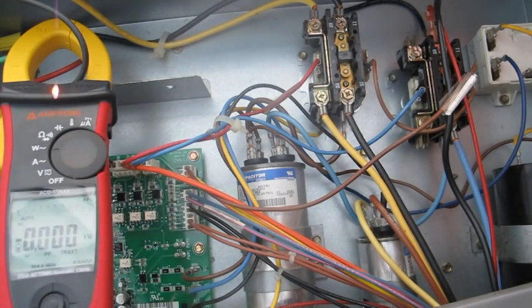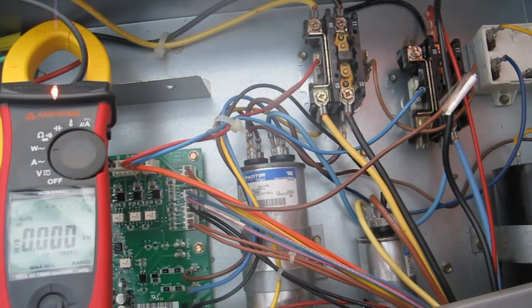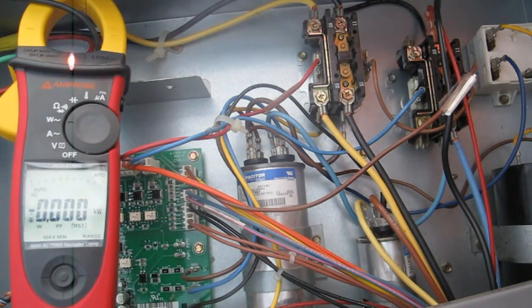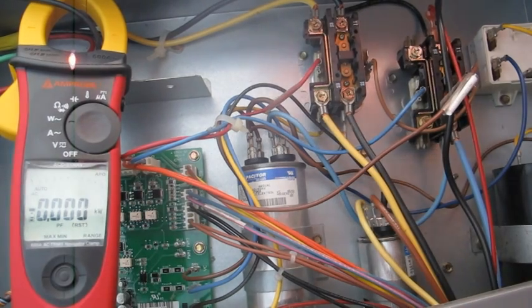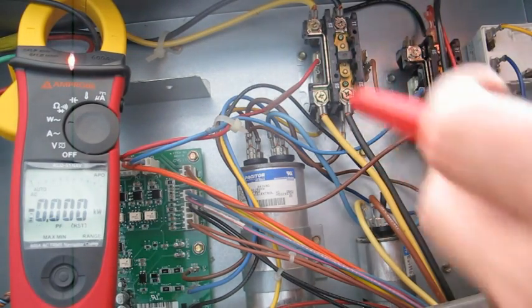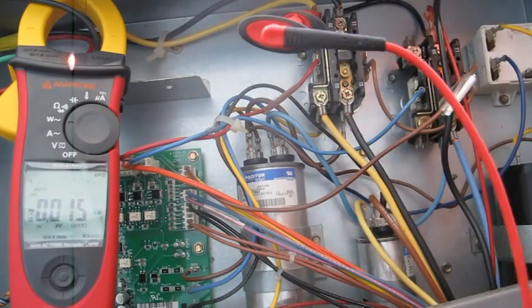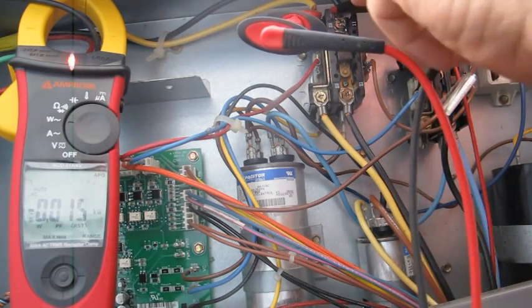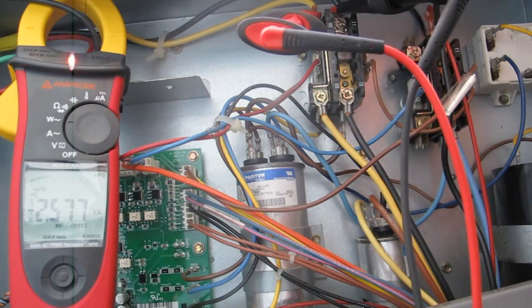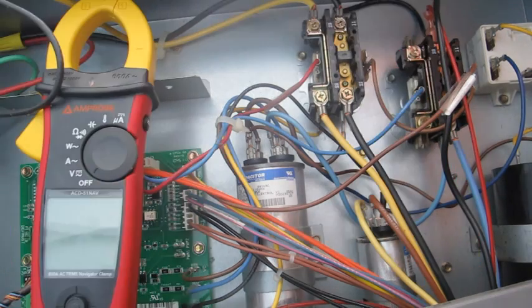To determine watts, all you need to do is get your voltage and your amp draw and multiply the two together: voltage times amps equals watts. With this particular meter, all I have to do is clamp around one of my hot wires and hook my leads to L1 and L2, and that gives me my watts, my kilowatts. To get watts from kilowatts, you just multiply by a thousand.